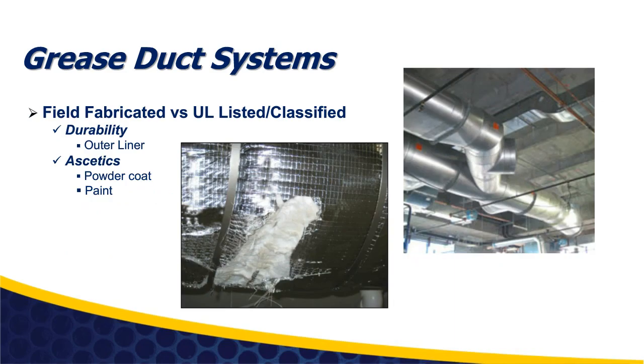So if I look at the installation of a wrapped ductwork, I really have concerns about its durability. Now I've got fiber insulation with a foil wrap on it. It's really critical that that insulation be in the right place and be intact to be able to perform its duty to remain as fire protection as it should.